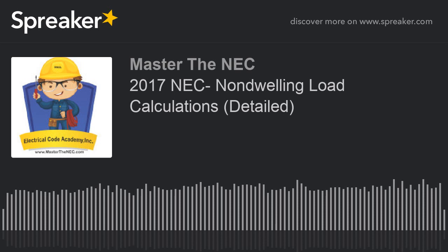So a feeder or service calculation can never be smaller than the combined rating of the two largest kitchen equipments in a load. And that's in 220.56. That's that last little paragraph that reminds me of that. Okay? Don't let that bog your mind, because that's probably rarely ever going to be a situation, but you just need to be aware of it.